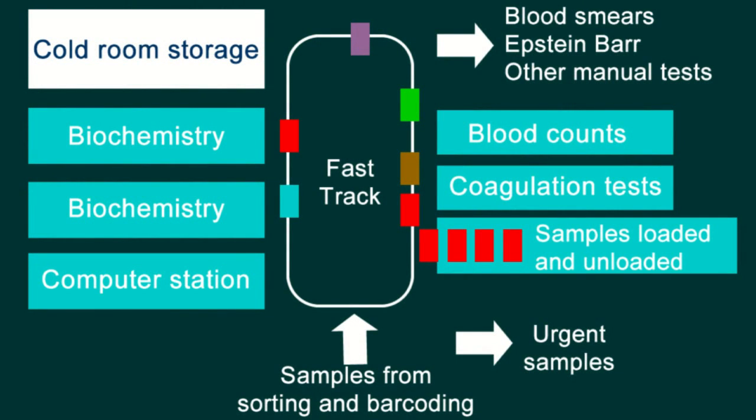The FastTrack system at the Leicester Royal Infirmary really is a stroke of genius. It's manufactured by Siemens and is essentially a huge oval track on which blood samples are manoeuvred around. They're placed in little things called pucks, which are just little capsules that float them round on the system, and their whole fate is directed by which barcode the biomedical scientist has placed on the sample — so the sample might go off for coagulation, cell counts, or biochemistry.